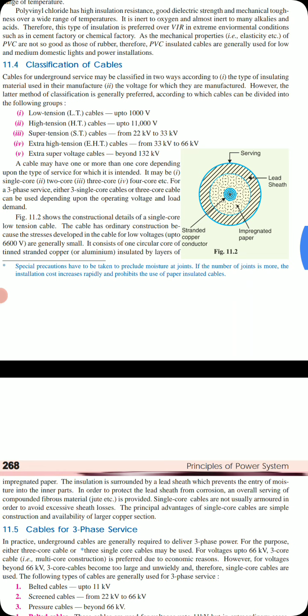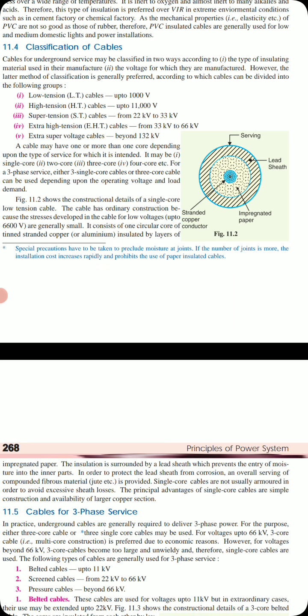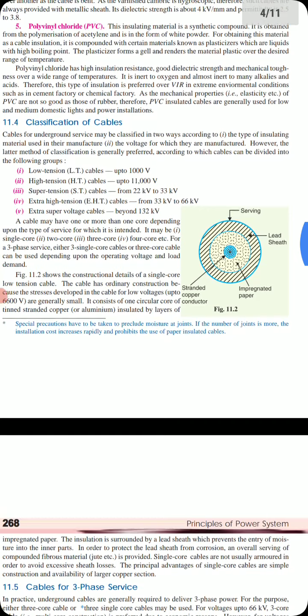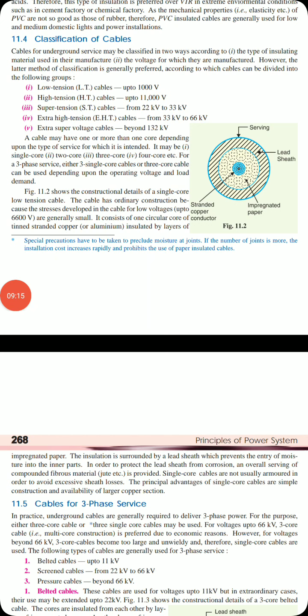Single core cables are not usually armored in order to avoid excessive sheath losses, because armoring is not used here as it is meant for very low tension or very low stress purposes. The principal advantages of single core cable are simple construction and availability of a larger copper section. This is one of the important things about the single core cable. Okay, so the remaining things we will see in the next class.